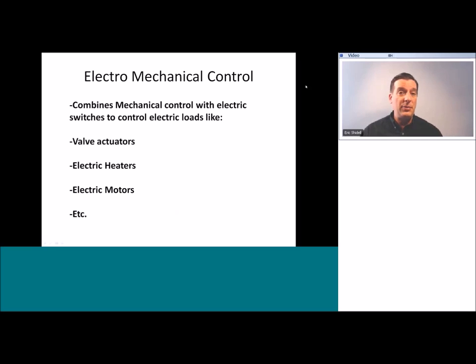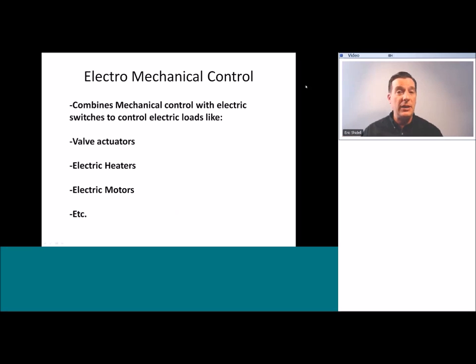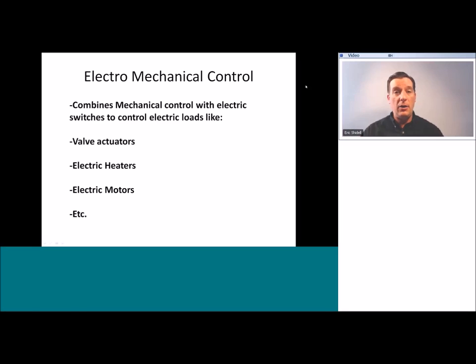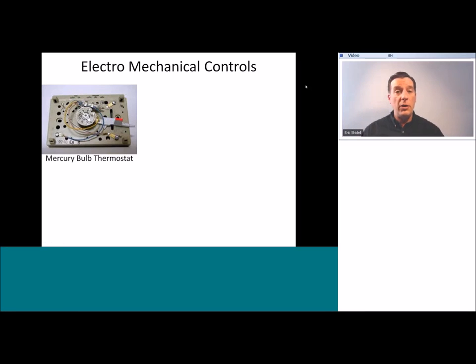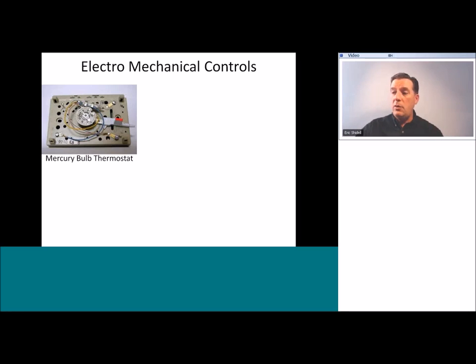The next level of control that has begun to replace mechanical is electromechanical, building off of what came before. Electromechanical control combines the mechanical sensing element — something moving in response to temperature — with an electric switch. So now instead of that movement directly operating a valve, it operates a switch, which can then electrically control a valve, motor, or heater. A good example is the mercury bulb style thermostat, where a temperature-sensitive bimetal coil moves in response to temperature changes, causing an electric mercury switch to make or break a set of electrical contacts.